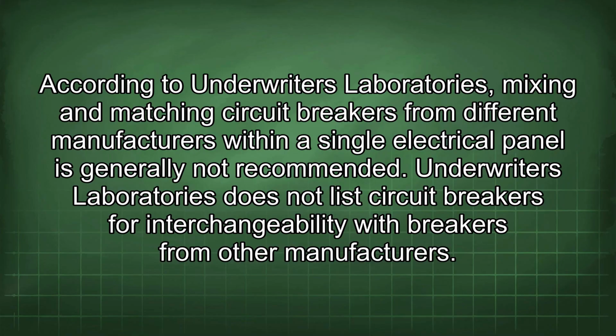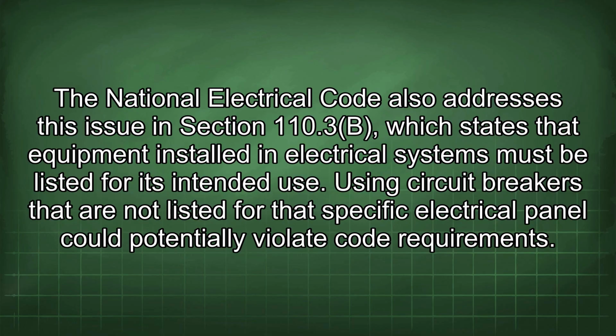According to Underwriters Laboratories, mixing and matching circuit breakers from different manufacturers within a single electrical panel is generally not recommended. Underwriters Laboratories does not list circuit breakers for interchangeability with breakers from other manufacturers. The National Electrical Code also addresses this issue in Section 110.3(B), which states that equipment installed in electrical systems must be listed for its intended use.